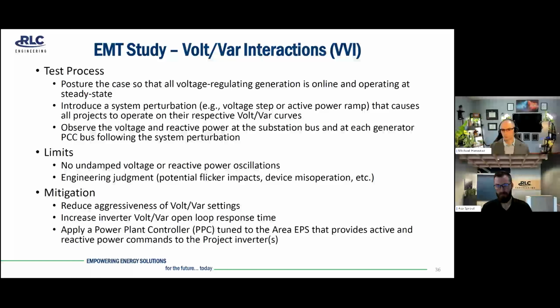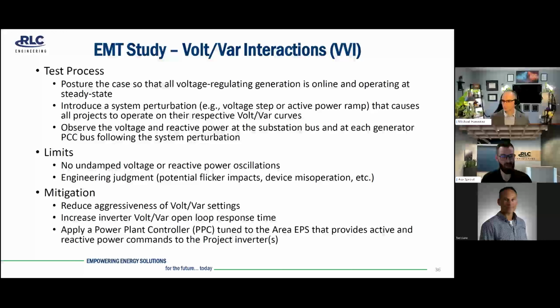impacts or device misoperation. The mitigation strategies, one, if it's possible, we would reduce the aggressiveness of volt-var settings, or essentially make the proportional response to a voltage deviation a bit less by adjusting the volt-var setting slope. That's not always an option because sometimes we're limited based on the traditional evaluation that Mike already covered. So a second option would be to increase the inverter volt-var open loop response time. This is typically a 5-second window per 1547, but I believe they can go up to 90 seconds while still being in that criteria. But if you go too high, you also want to make sure you're coordinating with the tap delays of your LTCs, regulators, and switched capacitors if they're on the system. The third mitigation strategy would be applying a power plant controller, or PPC, that's properly tuned and can provide real and reactive power commands to the project inverters rather than the inverters doing it locally or through their terminal readings.